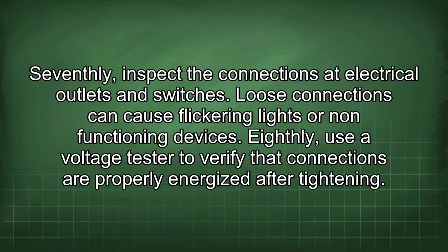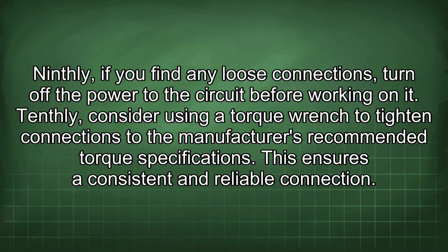Seventhly, inspect the connections at electrical outlets and switches. Loose connections can cause flickering lights or non-functioning devices. Eighthly, use a voltage tester to verify that connections are properly energized after tightening. Ninthly, if you find any loose connections, turn off the power to the circuit before working on it. Tenthly, consider using a torque wrench to tighten connections to the manufacturer's recommended torque specifications. This ensures a consistent and reliable connection.